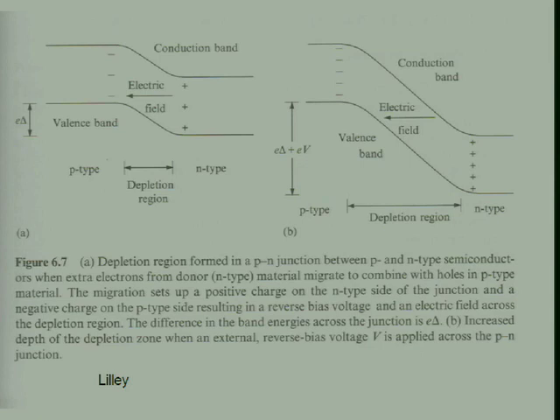And so in this germanium detector in here, this one's about 2 inches in diameter and about 2 inches long. And we're going to put 3,200 volts across it. And we'll create a depletion region which occupies almost the entire volume of that crystal. And so what that means is then when photons come in and interact anywhere in there and produce ionization, we'll sweep the charge out and measure the size of the current signal and get a good measurement of the energy. And a similar thing happens for silicon detectors.